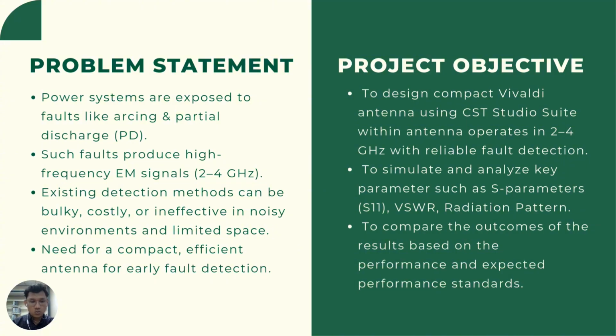Okay, we want to tell you about the problem statement and the objective. First, the problem statement. Power systems are exposed to faults like arcing and partial discharge. Such faults produce high frequency electromagnetic signals in the range of 2 to 4 GHz. Existing detection methods can be bulky, costly, or ineffective in noisy environments and limited space. There is also a need for a compact, space-efficient antenna for early fault detection.